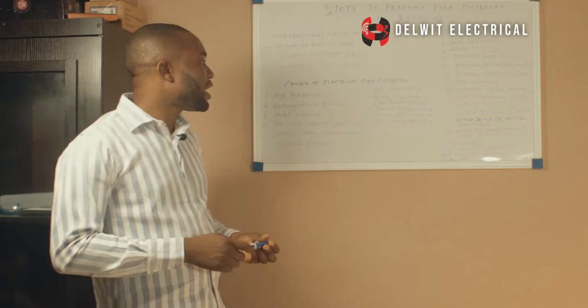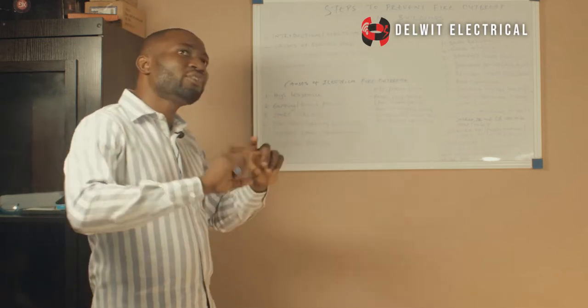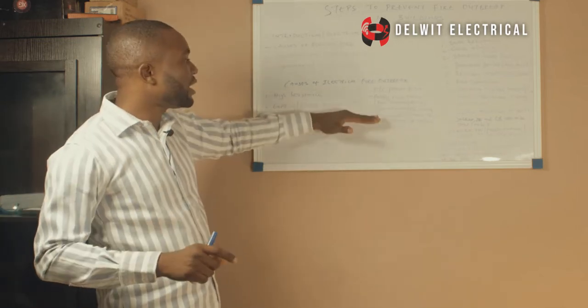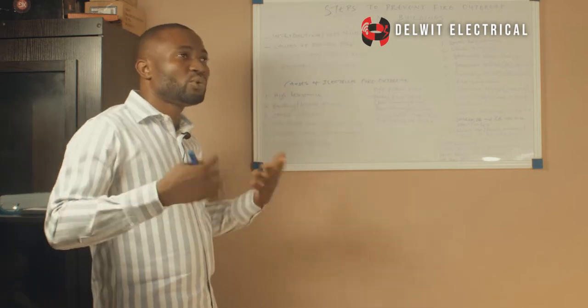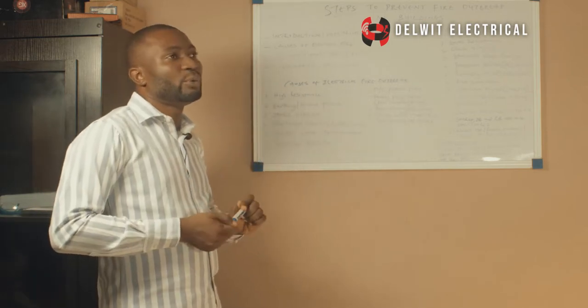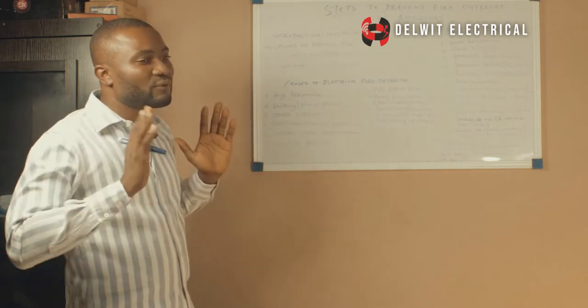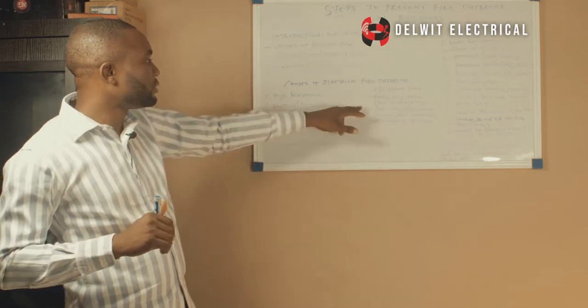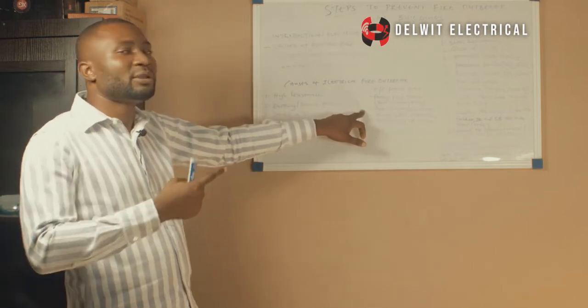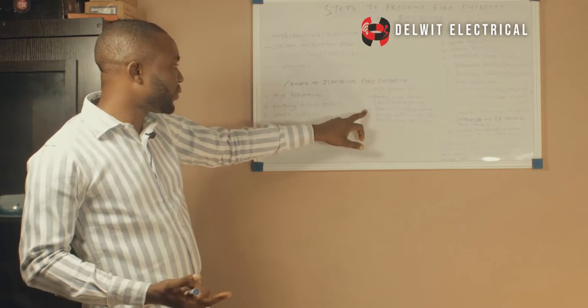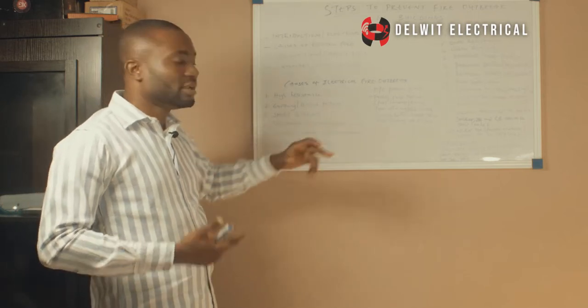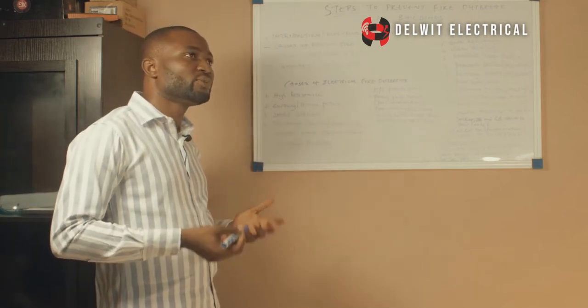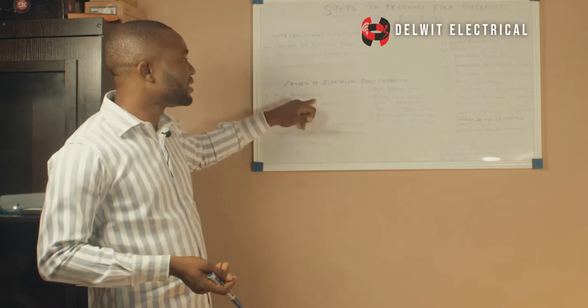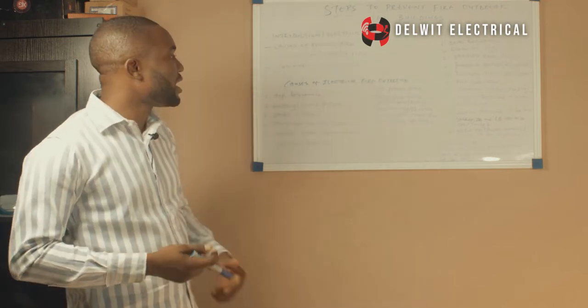The third one is poor wiring or old wiring. Now, wiring of buildings is very important. But if the wiring is poor, or those olden days wiring that we have, I believe those olden days we had good copper content wires, but because of the usage of that time, it might not have the adequate rating that is required. So if you have poor wiring, it's ideal that you change it to standard wiring to avoid high resistance that will lead to fire outbreak.